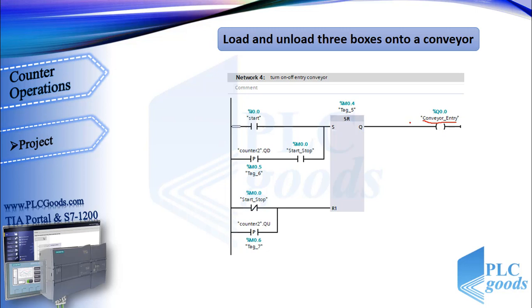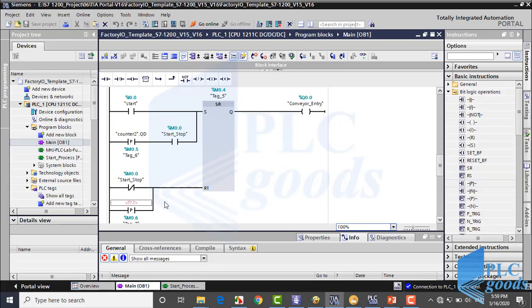In the next network, I've used an SR flip flop to turn the first conveyor on and off. It will be on if the start push button is pressed or there are no boxes on the buffer conveyor — but I don't want to turn this conveyor on when the start-stop memory is off. It will be off if the stop push button is pressed or there are three boxes on the buffer conveyor. Pay attention to how we refer to output QU of the counter — when this output is on, it means the current value is equal to or greater than the preset value, meaning there are three boxes on the buffer conveyor.